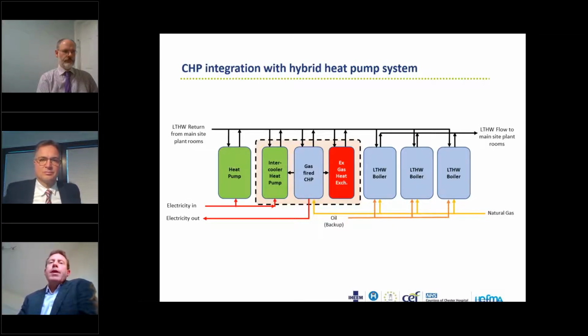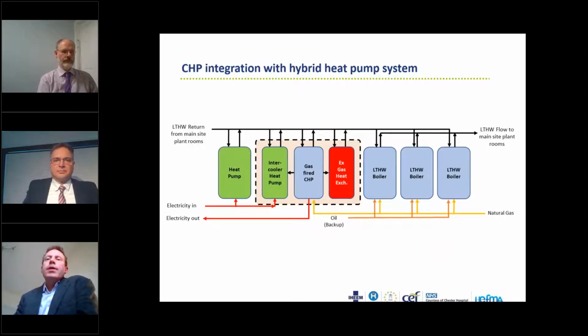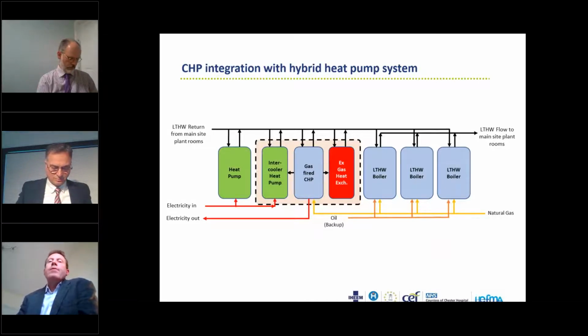It's got intercooler heat, so it's taking the intercooler heat, upgrading it with another heat pump, putting that back into the return, and then finally the exhaust gas heat exchanger, putting the third component of CHP back into the network. Hopefully those low temperature hot water boilers are going to spend very little time doing any serious hard work, except maybe in the peak of winter.